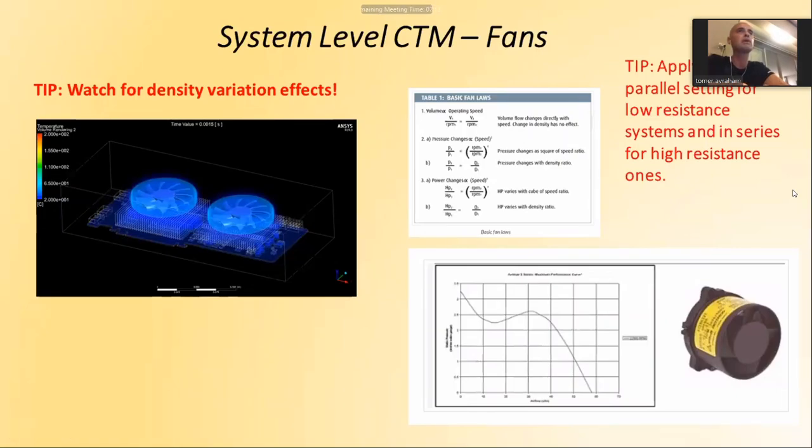It's not only the amount of flow that you need, it's whether you need to work at height, because the curve, this curve you see here, goes down as the density, divided by the density at sea level.